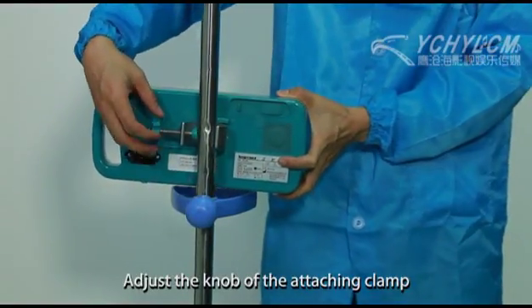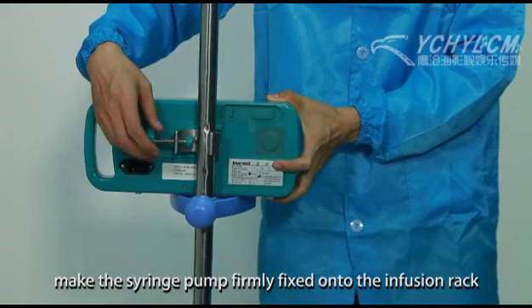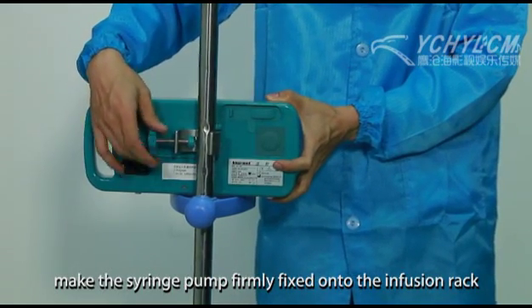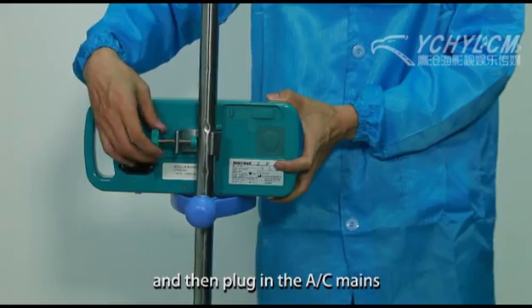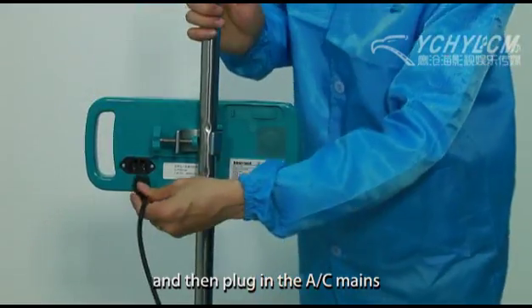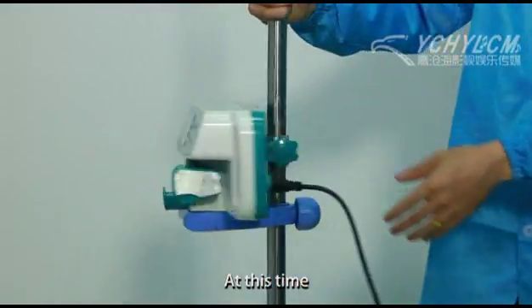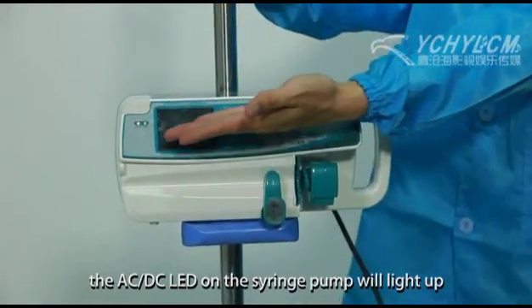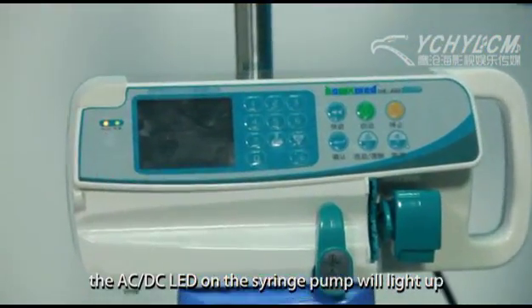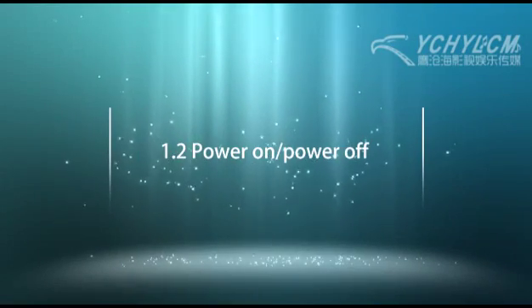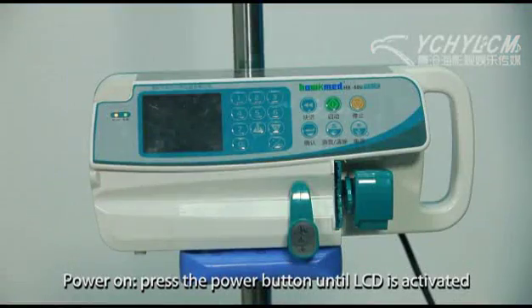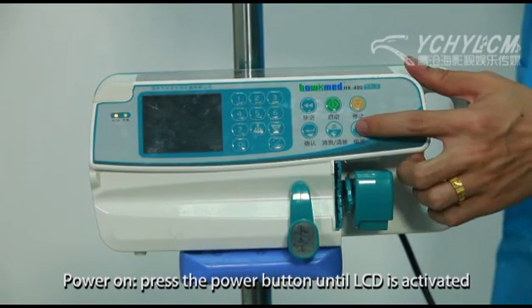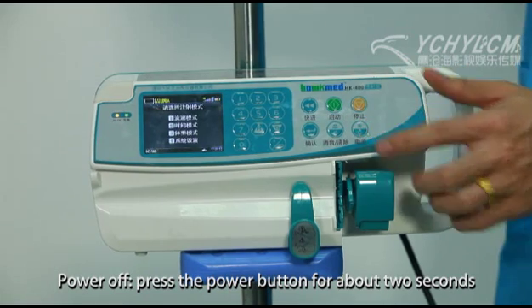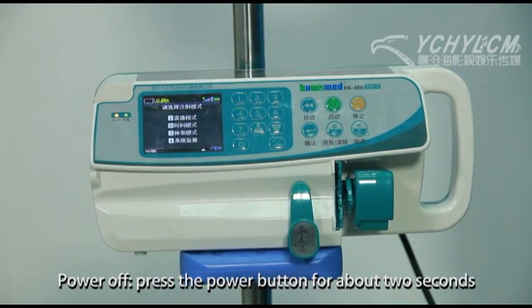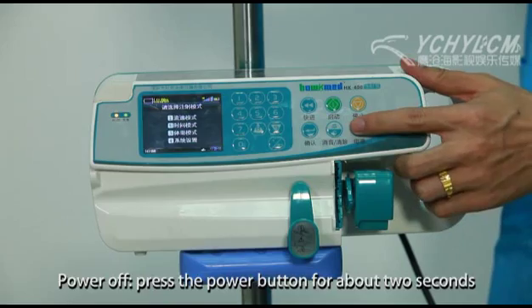Adjust the knob of the attaching clamp. Make the syringe pump firmly fixed onto the infusion rack, and then plug in the AC mains. At this time, the AC/DC LED on the syringe pump will light up. Power on: press the power button until the LCD is activated. Power off: press the power button for about 2 seconds.